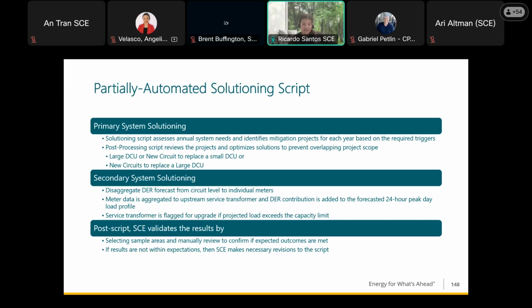Within the primary solutioning, the post-processing script then reviews the first 10 years of needs for each sub and advances large distribution circuit upgrades or new circuits to replace small DCUs in an earlier year. For example, if small DCUs are identified in, say, years 3 through 5, but a large DCU is required in years 6 through 7, then the script will show that a large DCU is needed from years 3 through 7. This is aimed at identifying the most cost-effective solution for multiple years of needs.